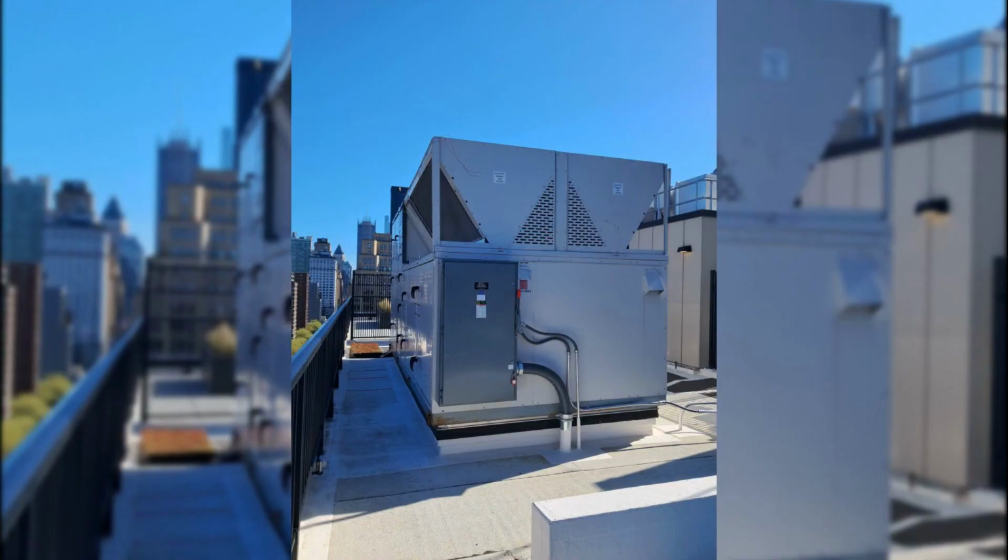Section 6.2.13, Arrangement and sizing of HVAC equipment. Heat pumps, DX or dual temp with approved chillers, required for all spaces. Heating: size units for the 12.8 degrees Fahrenheit outdoor air design condition, not at the AHRI 47 degrees Fahrenheit rating. Boiler-based systems need special approval. Cooling: includes sensible and latent loads, must handle spring transition conditions.